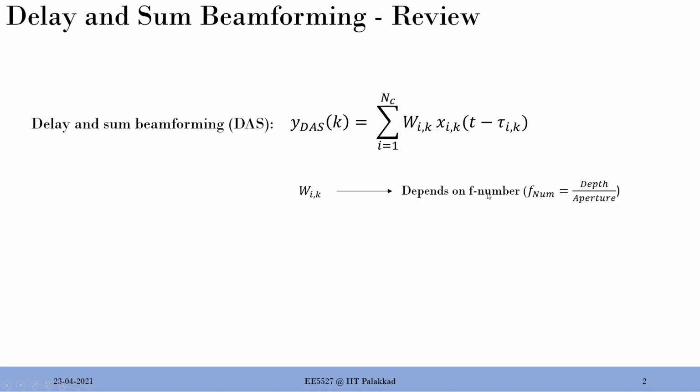That aperture decides how many transducers you have to select, and then you can use a Gaussian or a Hamming or a Hanning shape, so that the shortest sensor to the pixel will be given the highest weight, and so on. But overall the major takeaway is that w_ik can be calculated beforehand, because it is just dependent on the geometry. There is no other dependence on it.